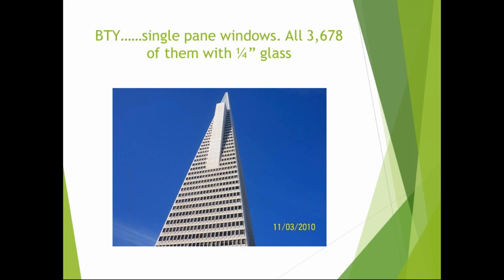Let's pretend this is my building. I have 3 feet of return air. That 3 feet of return air is conditioned, right? We spent money to condition it. It goes back to my systems. I either get rid of it or reuse it through my economizer system. Well, that's going through the skin of the building, touching the surface of that cold or warm concrete. So that's another thing you have to fight on.